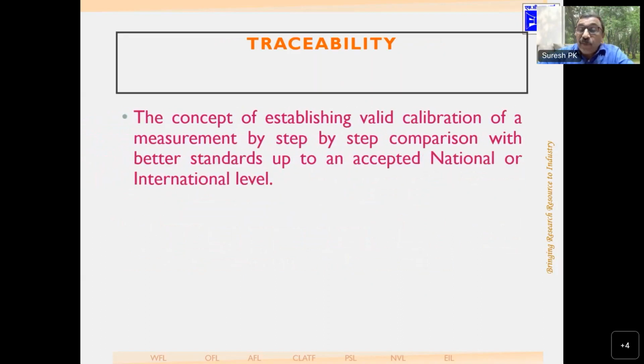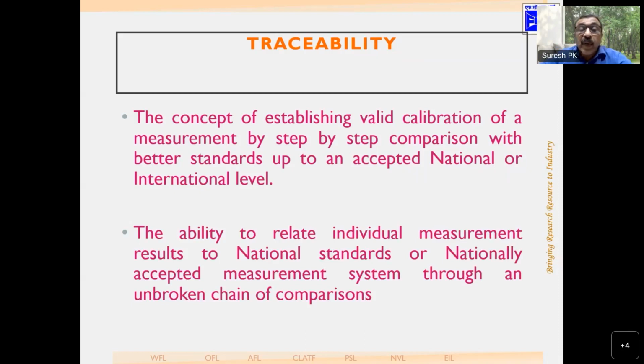Now, the traceability. The concept of establishing a valid calibration of a measurement by step-by-step comparison with the better standards up to an accepted national or international level. So, the ability to relate individual measurement results to national standards or a nationally accepted measurement system through an unbroken chain of comparison. This is important. When legal metrology says that you have to calibrate your instruments once in a year, that means they are insisting for you to keep your unbroken chain of comparison.